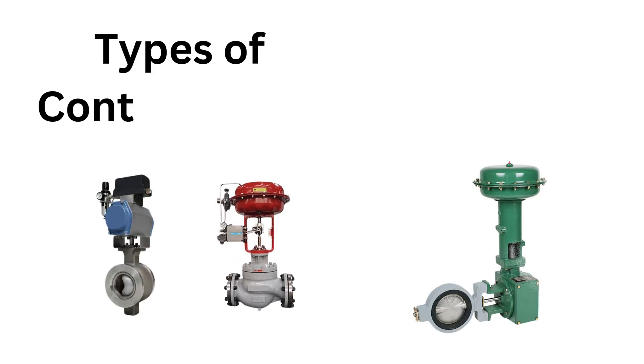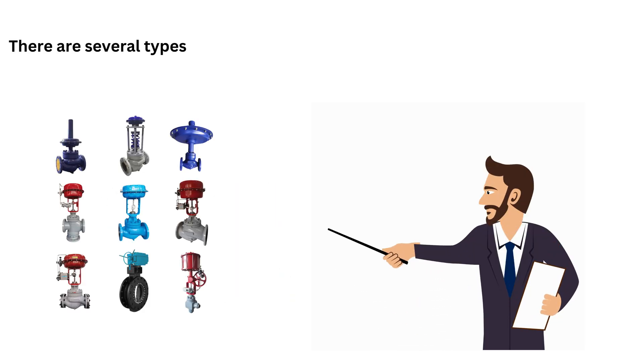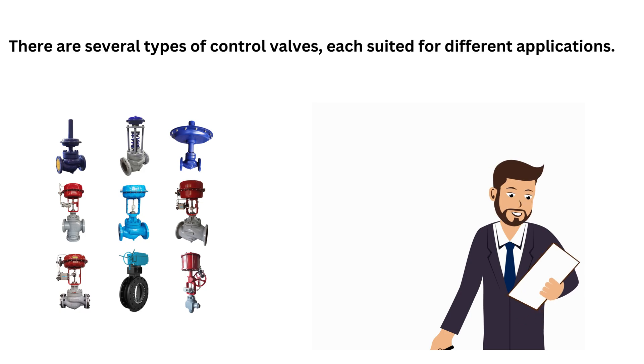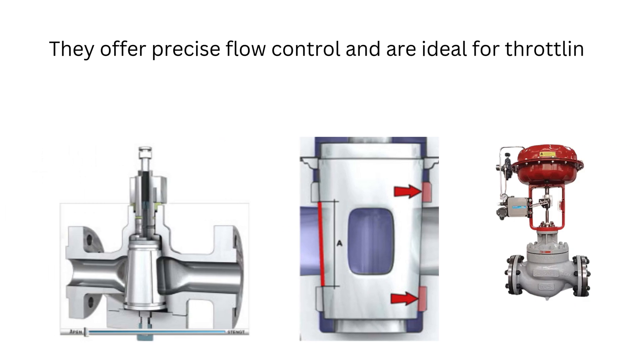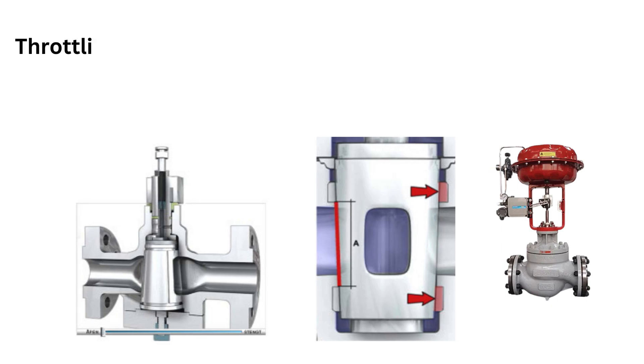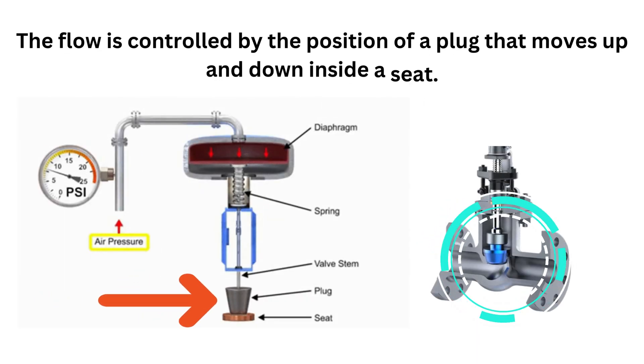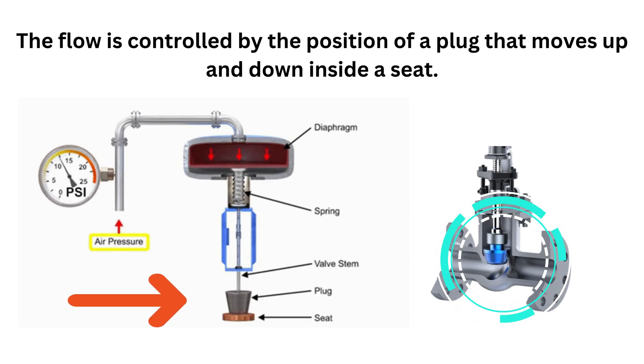Now let's discuss the types of control valves. There are several types, each suited for different applications. The first one is globe valves. Globe valves are the most commonly used control valves. They offer precise flow control and are ideal for throttling applications. Throttling is the process of limiting the flow of something, such as a fluid. The flow is controlled by the position of a plug that moves up and down inside a seat.